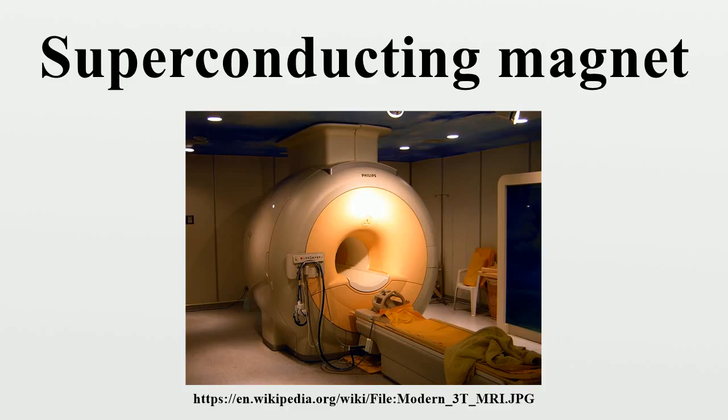One high-resolution mass spectrometer is planned to use a 21 Tesla superconducting magnet. Globally in 2014, about €5 billion worth of economic activity resulted from applications for which superconductivity is indispensable. MRI systems, most of which employ niobium-titanium, accounted for about 80% of that total.